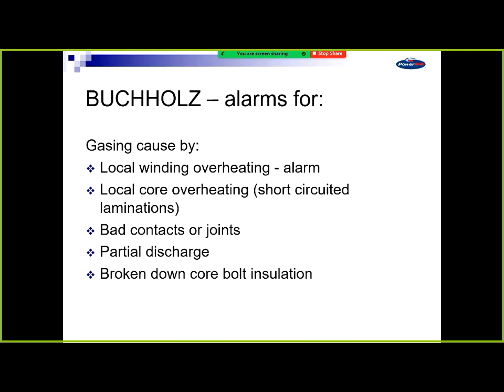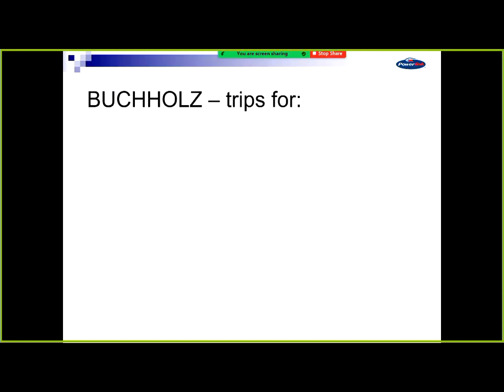For PowerLink, we reduce the risks as much as we can. We take oil samples. We've got a really good lab, which is probably one of the better ones in Australia, that do the testing of all the oil samples and can tell from that how the age, the insulation, how the transformer's going. So we can know it. You can have transformers which have physically been there longer but look younger than younger transformers, which may have been heavily loaded in their life. So these sort of oil tests give us a condition monitoring of the transformers. When you've got a big network and a lot of transformers, it pays to invest in things like that.